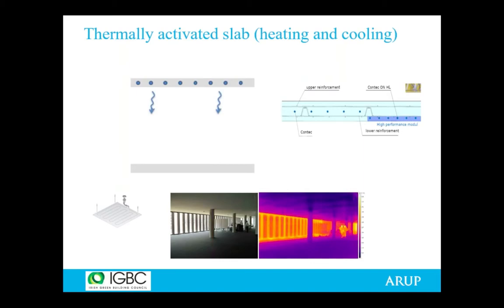They want water relatively not very hot, sorry. They like to supply water at 40, 45, 50 degrees. If you supply with a heat pump at water over 60, 70, then the heat pump doesn't like it in terms of efficiency. So you can supply water to the slabs at maybe around 30 degrees, 20 degrees, and you still can heat the building. Obviously, this system requires exposed slabs, exposed surfaces, so the warmth of the slab gets into the occupants.